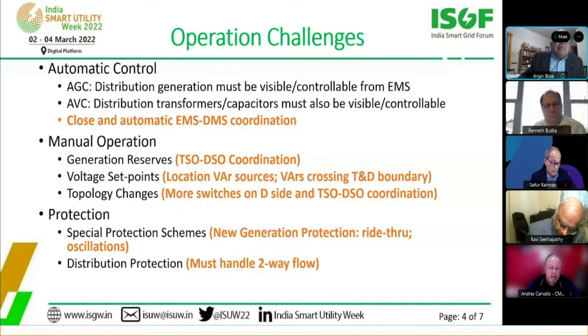But now that gets much more complicated if a lot of this generation is on the distribution side. The normal operational process says voltage control on the transmission side is usually under the transmission operator, and voltage control on the distribution side is opposite. But we will come into situations where we may not have enough VARs on transmission and distribution to do completely separate kinds of controls between transmission and distribution.